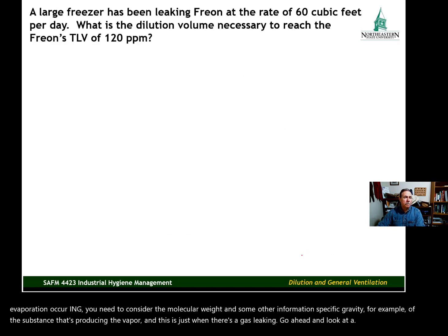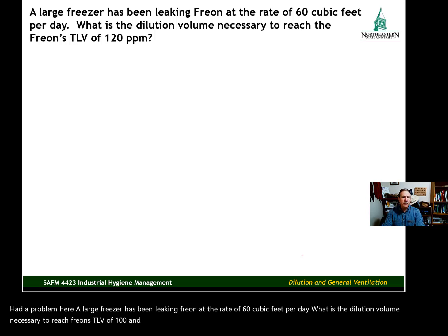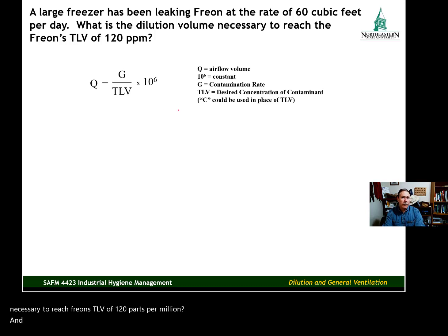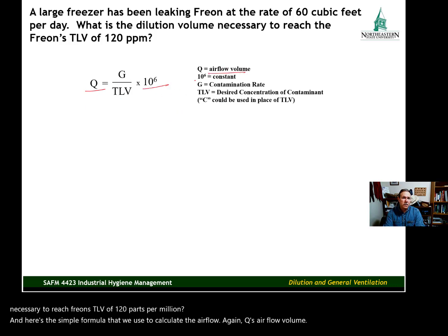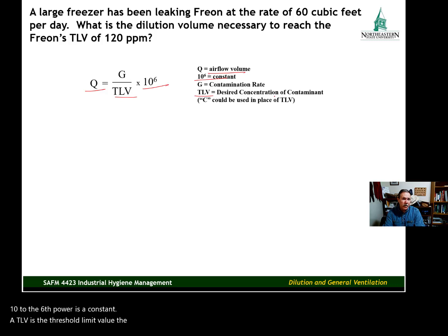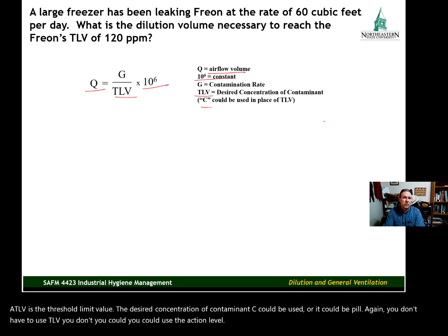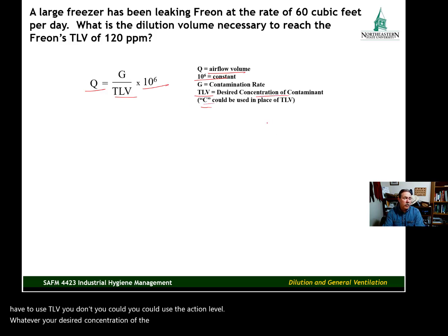Let's look at a problem. A large freezer has been leaking Freon at the rate of 60 cubic feet per day. What is the dilution volume necessary to reach Freon's TLV of 120 parts per million? Here's the simple formula: Q is airflow volume, 10 to the 6th power is a constant, and TLV is the threshold limit value — the desired concentration. You could also use the action level or PEL as your target concentration.